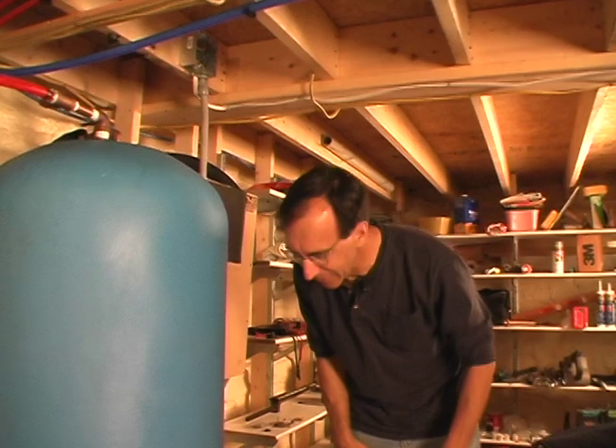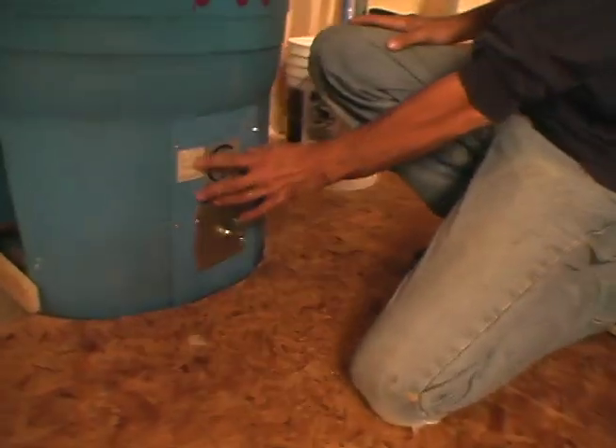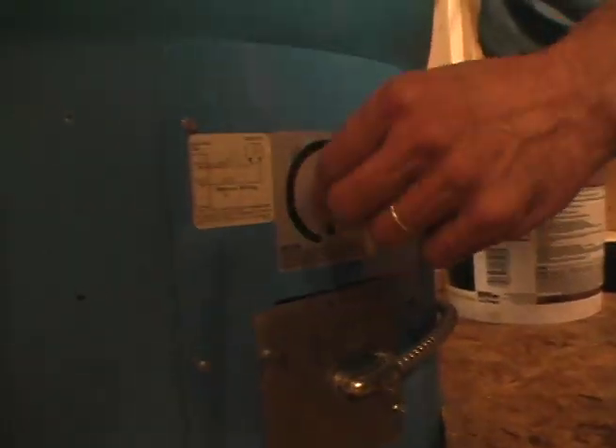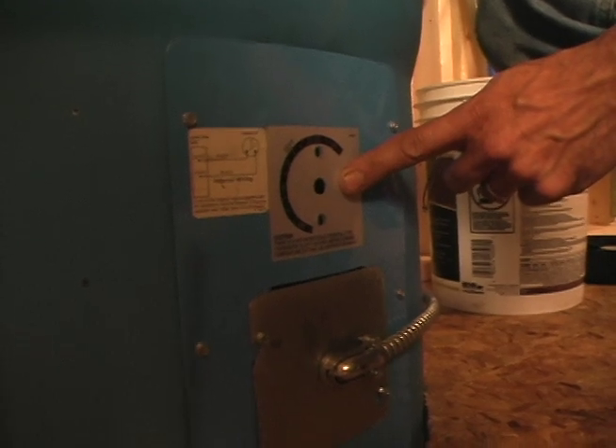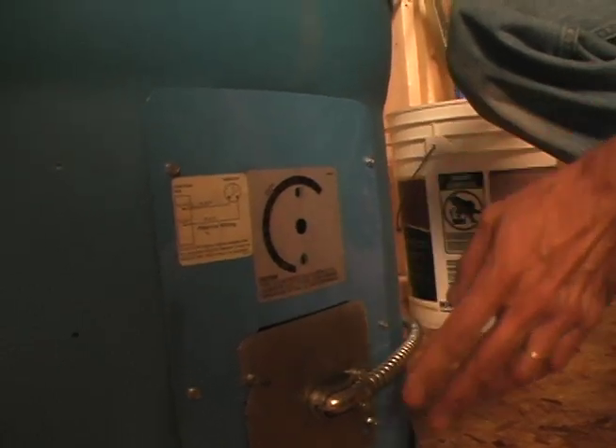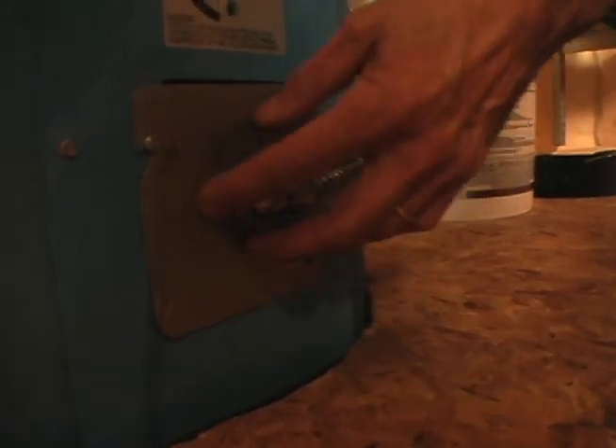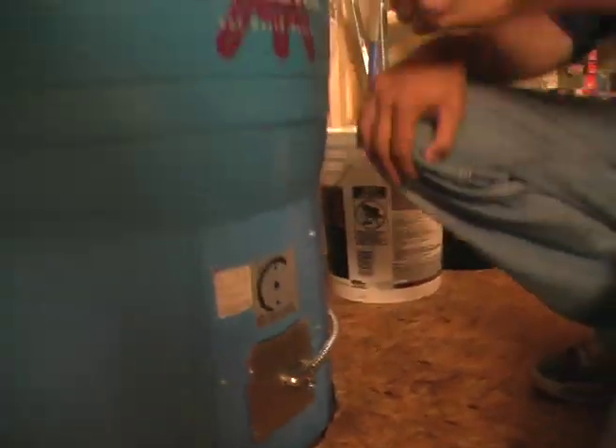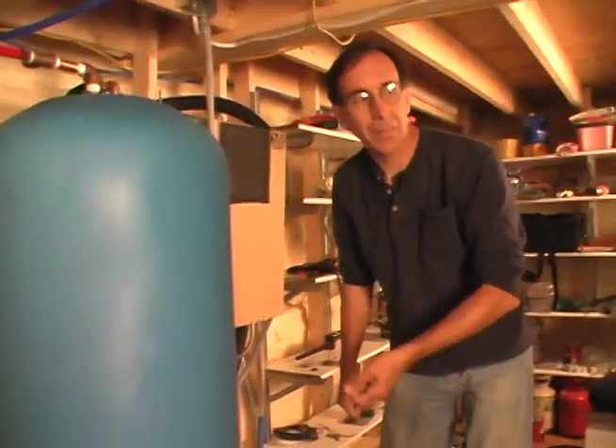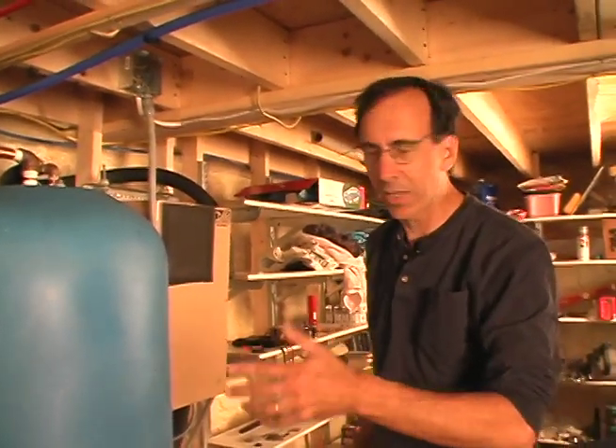The controls are a little bit different. We have an aquastat down here. The original aquastat that was on this tank, which had a knob for adjustment, was defective, so I've bypassed it, and behind here I have an aquastat installed that is adjustable, so I can make hotter or colder water depending on what it is.